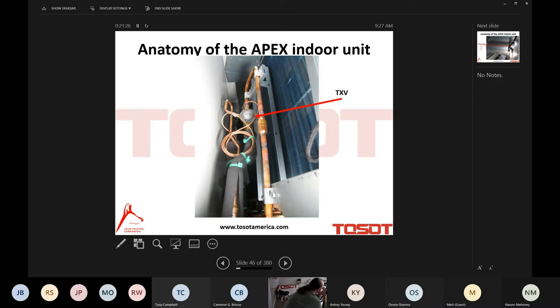You can match the Apex outdoor unit with any 14 SEER or better R410A fan coil. It's a beautiful thing. We'll talk a little bit about dual fuel applications, which I know is big up in Canada. And we also now have just a coil option as well, where you don't have to buy the Apex fan coil unit. You can just buy a traditional A coil as well. The bottom line, no matter who makes it, no matter who you buy it from, no matter what the manufacturer is, if you're going to use someone else's indoor unit, whether it be an A coil or a fan coil, it must be 14 SEER or better, and it must have a TXV. And again, we'll talk more about that in some detail as we move forward.